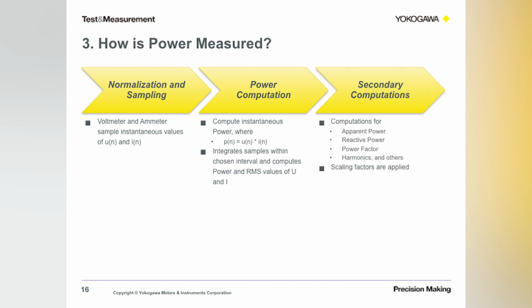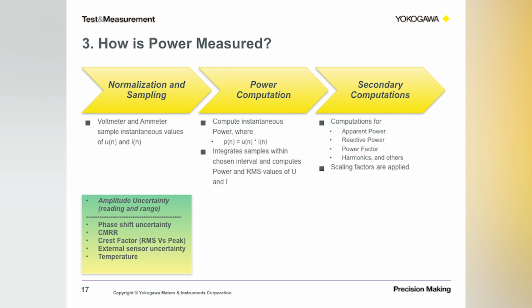Lastly, it'll perform secondary computations like calculating apparent power, reactive power, power factor, harmonics, and all different other types of parameters that are associated with power measurement. Scaling factors are applied as appropriate to give you those measurements in real time, right? So what is important in the first two steps out here?